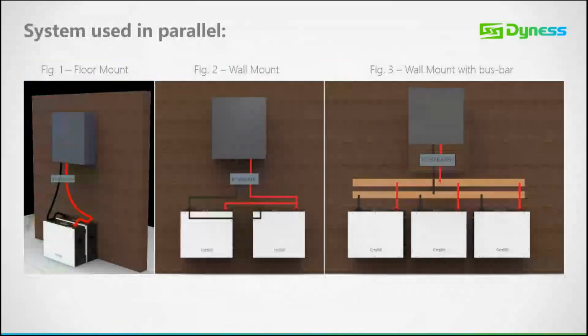When connecting our DL5.0C, your BX5100 and A48-100 in parallel, the following methods can be used. You have your floor mounting method, your wall mounting method, and your wall mounting method with a bus bar. When it regards to the bus bar, when 2 or more batteries are used in parallel, a bus bar is then needed. This bus bar needs to be spec'd according to the current rating of the system in use.